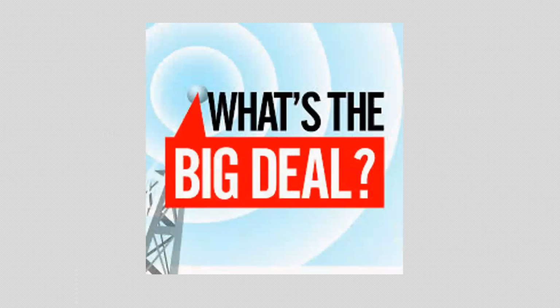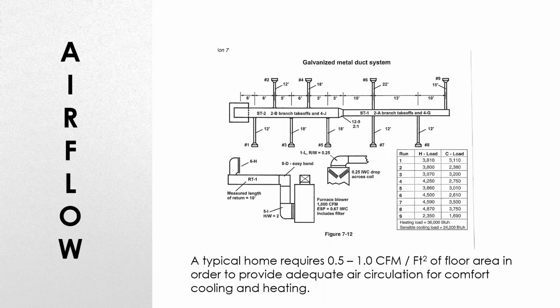So everybody says, what's the big deal? Well, the big deal is airflow. This is basically a system shown in Manual D, and it shows a furnace blower with 1,000 CFM and a 36,000 BTU heating load and a 24,000 BTU cooling load. So this is a home from either Middle America to Southern America, possibly. And so in this example they selected a 1,000 CFM blower.